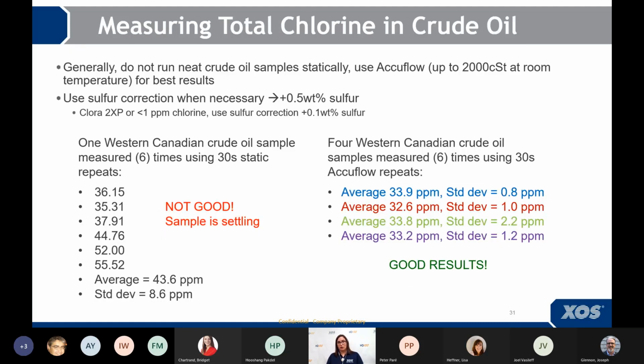Next, let's move on to chlorine. A lot of people know that chlorine doesn't behave the same as sulfur, especially when you're talking about crude oil. You typically have salts in crude oil, which are not stable. So if you were to take a raw crude oil, stick it into a sample cup, measure it for 5 minutes and walk away, you'll come back and the number will be high, because those chlorine salts are settling over time.